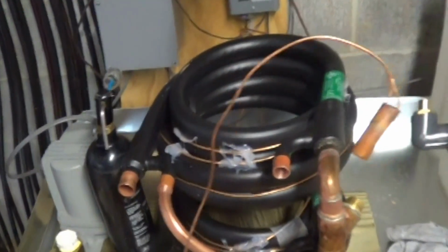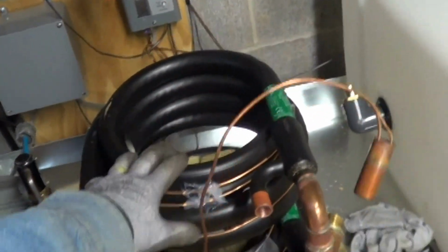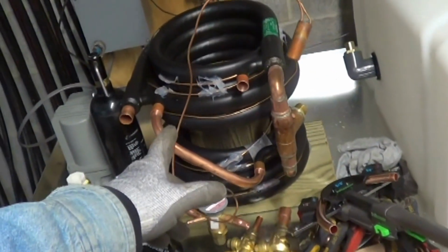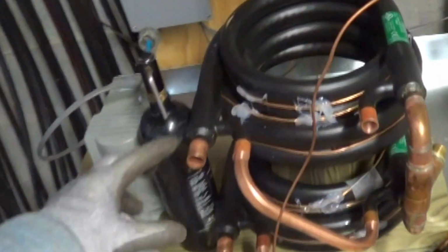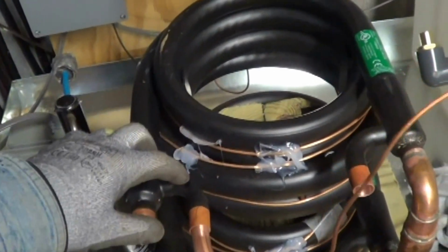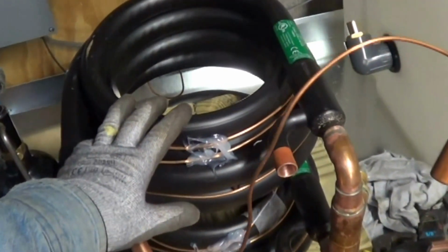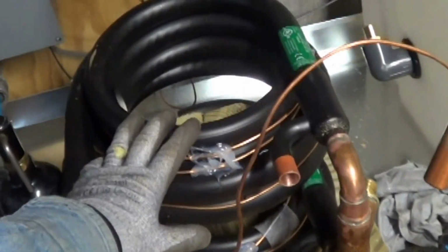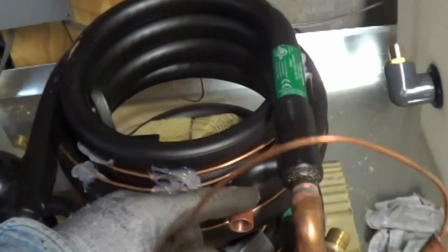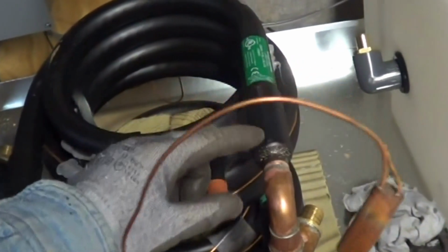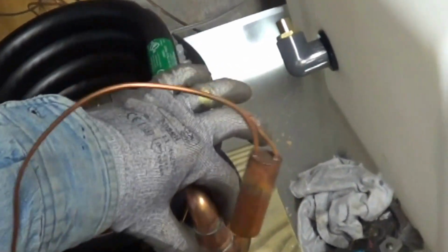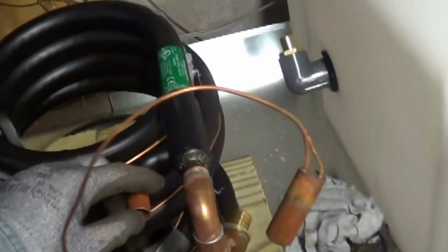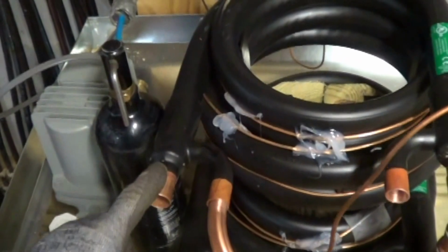So basically the way the system works is our heat pump is going to make our water hot, and we're doing counterflow. You always want to do counterflow. So we're doing counterflow for heating. We're not going to do cooling with this except defrost for a few minutes. So our hot gas is coming in on this side, and it's going to be touching the hot outlet. So that way the hottest gas is touching the hottest water. The coldest gas is touching the coldest water.